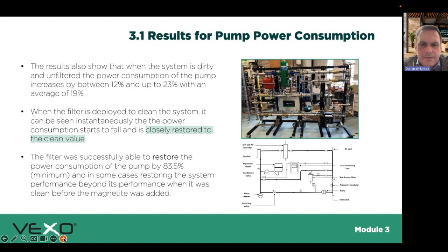There's just some slides here, mindful of time, but there's some slides of work we've done with Loughborough University - various analyses were carried out. We even saw savings, or restoring up to 83.5% of the energy use going into a pump. I have to say, bear in mind that's in a lab condition, so it's under a very much magnified condition. But the arbitrary number I'd say is you could be losing 19-20% on energy if you've got fouled strainers or poor water quality in your system.